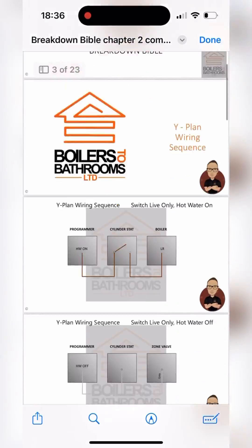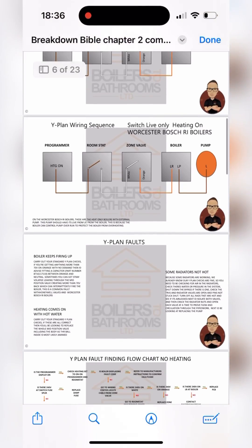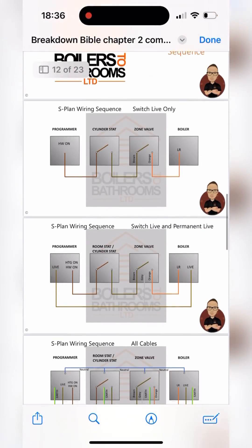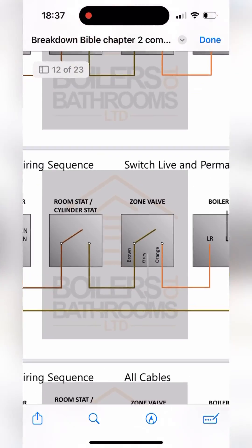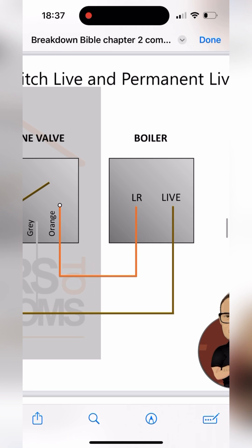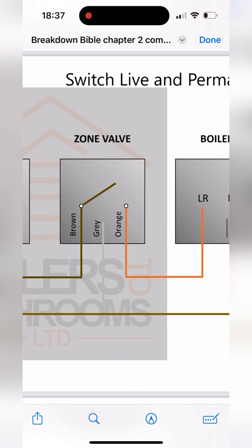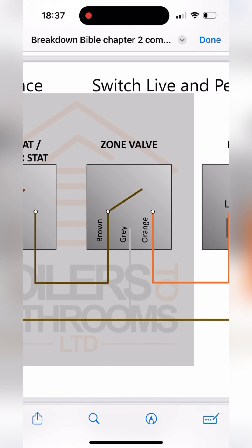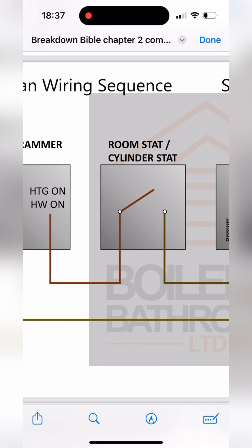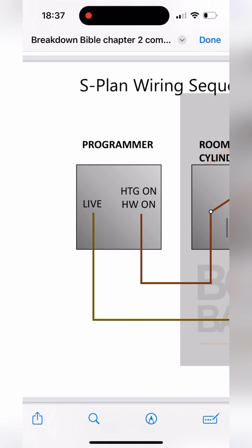Where do we start with a fault like this? Whip out the breakdown bible, go down to S-plan wiring sequences, and then we can see we're getting power to the boiler, which has to pass through the zone valve, pass through the cylinder stat or room stat, from the programmer.